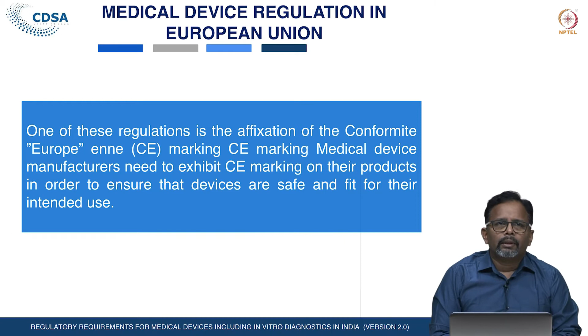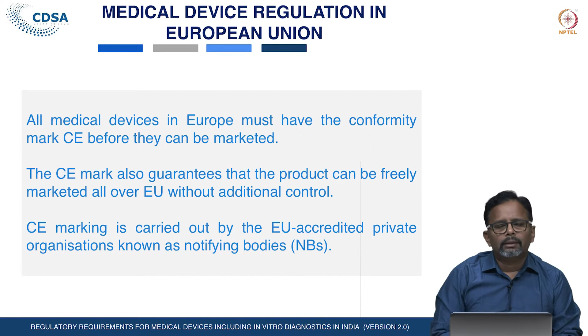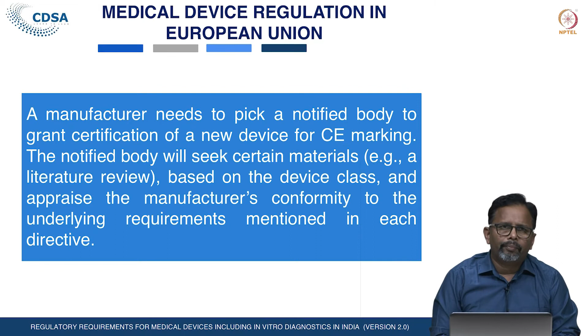All medical devices in Europe must have the CE conformity mark before they can be marketed, and this CE certificate also guarantees that the product can be freely marketed over the European Union without additional control. CE certification is carried out by a European Union accredited private organization known as a notified body. In Europe, the manufacturer can pick any notified body for grant of the CE certification, and the notified body will seek certain materials from the manufacturer, certain literature based on the device class. They will appraise the manufacturer's conformity to the underlying requirements mentioned in the European directive.